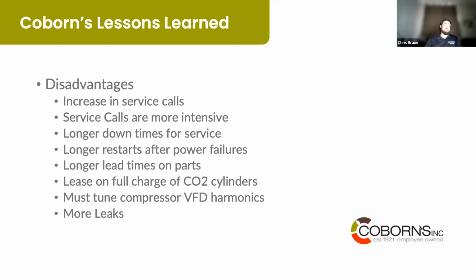Some of the disadvantages that we are seeing. We are seeing an increased amount of service calls. You've got case controllers. We didn't typically do case controllers on our HFC system. So we are seeing more service calls due to case controllers, right? You just have that much more data coming in. You're going to see that many more errors in data, right? So we're still trying to sift through that. Service calls tend to be more intensive; shutting down and fixing repairs on the CO2 system are more intensive, right? Because you have to be more careful about what you shut down, how long you shut it down for, just so you're making sure that you're not blowing off safeties.